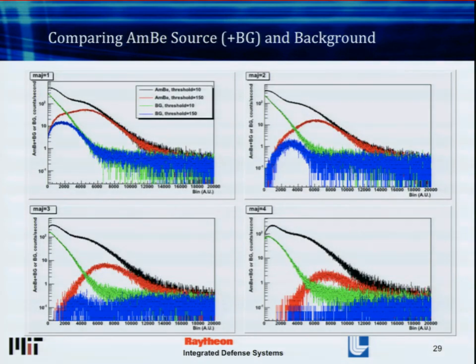Another thing to look at is the energy threshold, looking at the electronics. As I already mentioned, it's not always the best idea. It's always best to calibrate first and then determine based on your bin location, because things change. And using a combination of majority and electronic energy threshold, we can actually suppress background to the point where it's virtually non-existent in the low level.